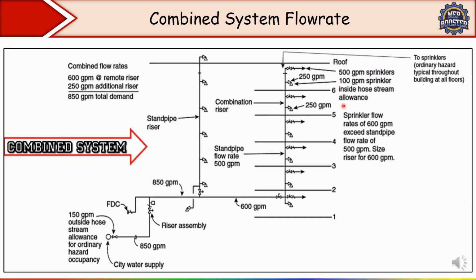Now let's say you have calculated the flow for sprinkler and you have got 500 GPM for sprinkler, plus 100 GPM sprinkler inside hose stream allowance, okay. So here we have a sprinkler flow rate of 600 GPM, which exceeds the standpipe flow rate of 500 GPM, okay. So the riser pipe size, the flow demand, we have to go for this 600 GPM, remember. This 600 GPM is the required flow rate for the most remote hydraulically sprinkler, okay. Clear this thing?